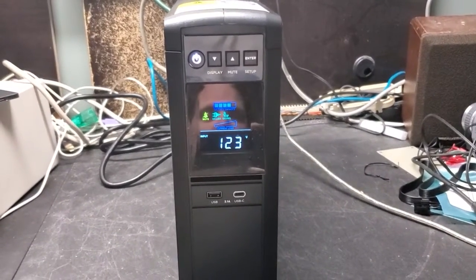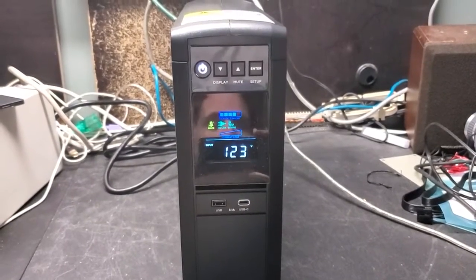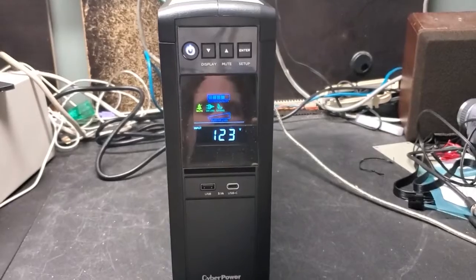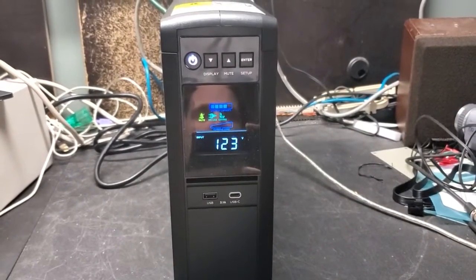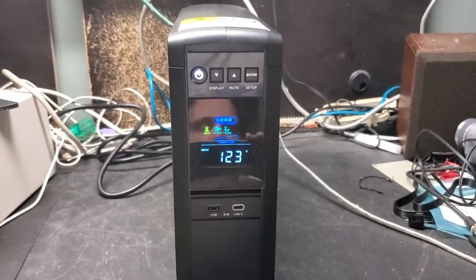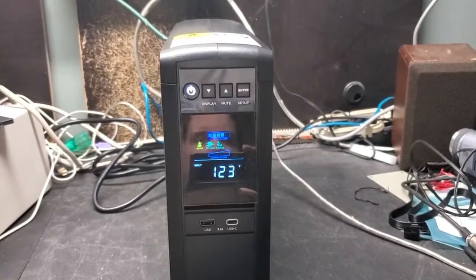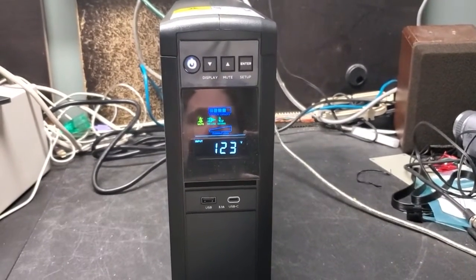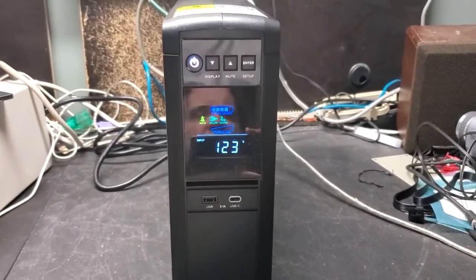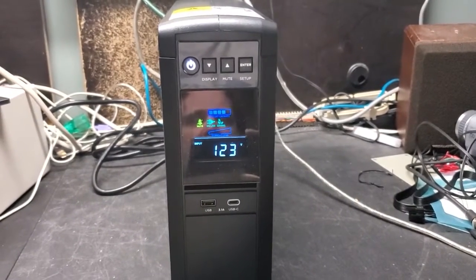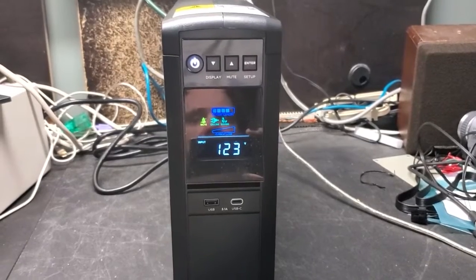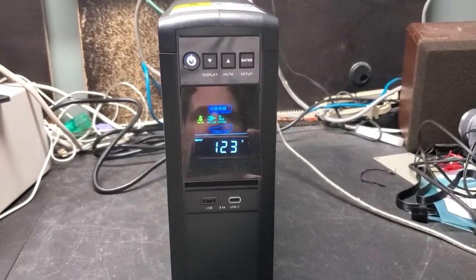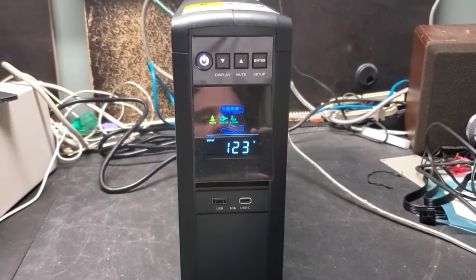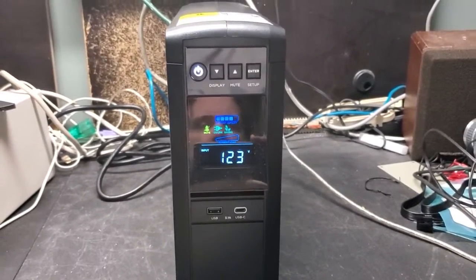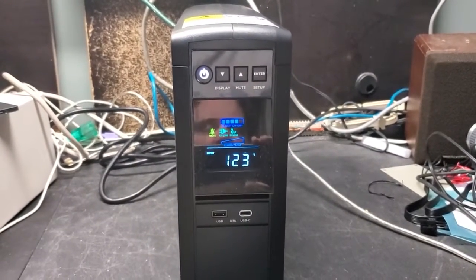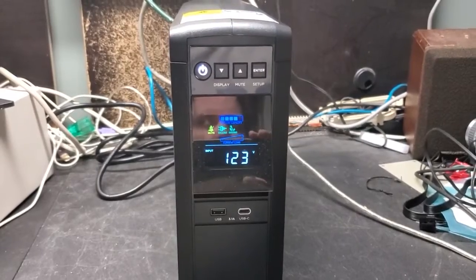In the case of a UPS that has a built-in voltage regulator like this one does, if the voltage of the mains power exceeds certain thresholds, the UPS will intervene, kick on its voltage regulator, and use it to boost or buck the mains voltage to the load. When that happens, the load is effectively being powered from the UPS. However, the UPS's AVR is still being powered by the mains power, not the battery power. So if the mains power varies in voltage too much, eventually the UPS won't be able to regulate the voltage with its AVR, and it'll just switch over to battery power completely.